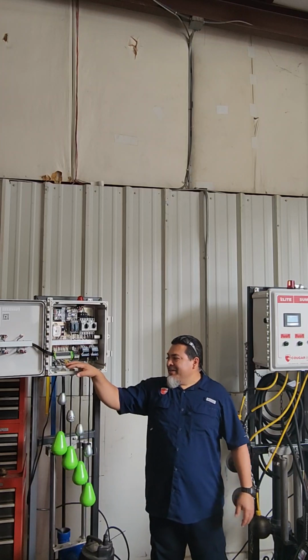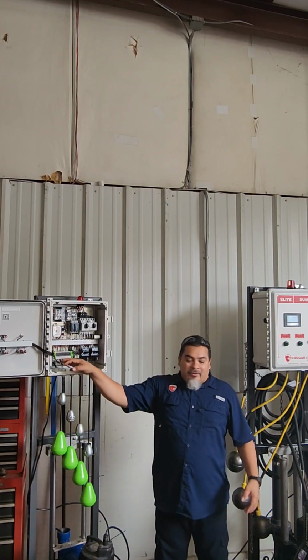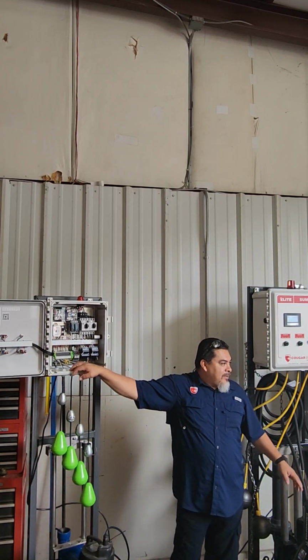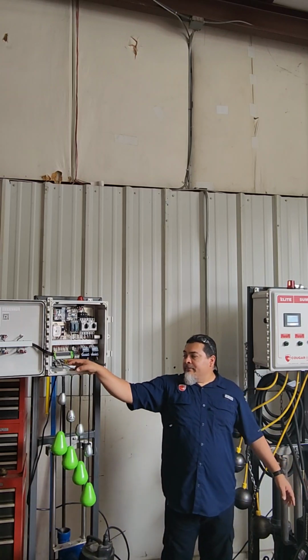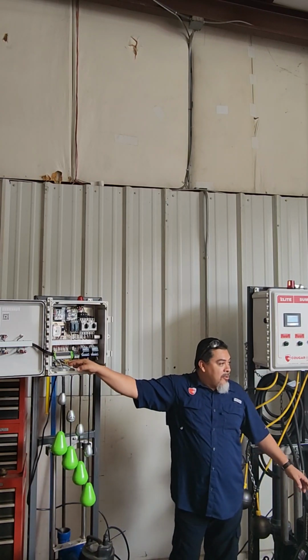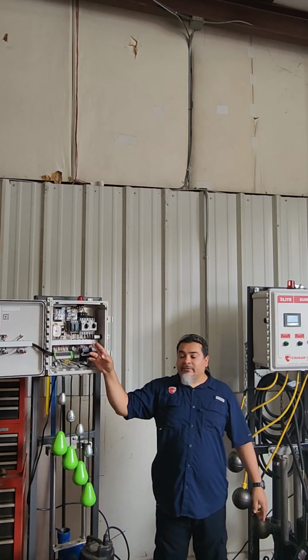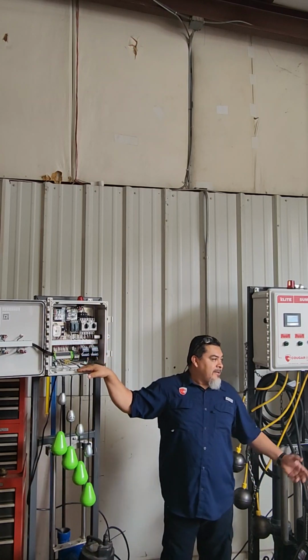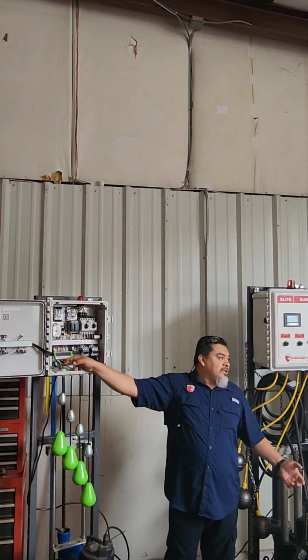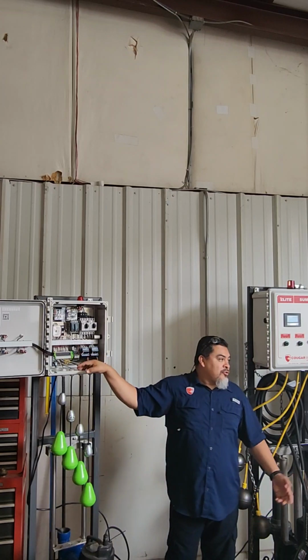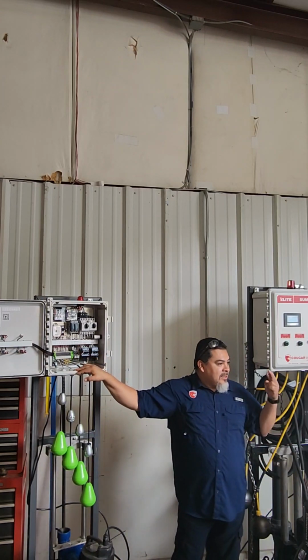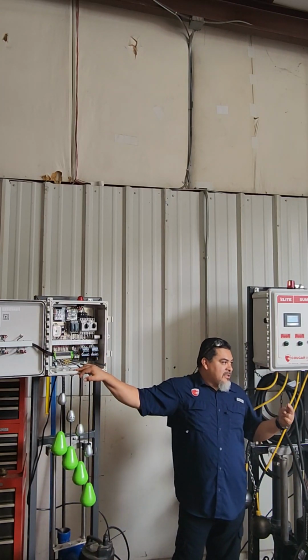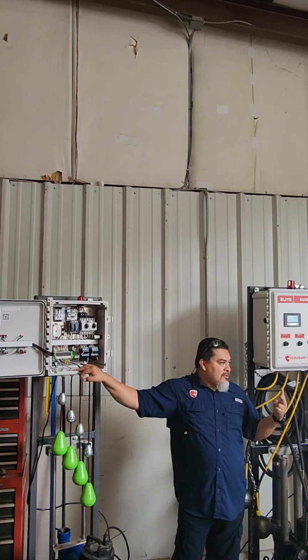Alright, so of course, each pump has a high temp. If for some reason the pump doesn't come on, even though you do have power on the panels and everything's good, and you can't find out what the issue is, and the overload's not on trip, there's a high temp switch that is always closed. So there's times that it fails and it stays open.